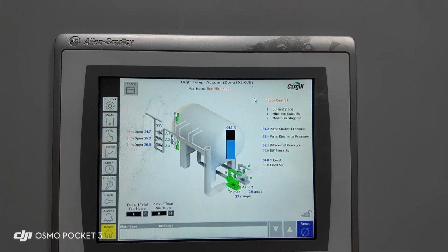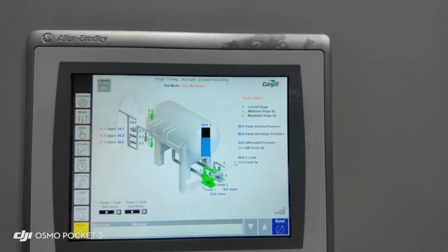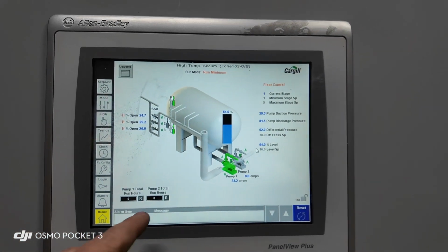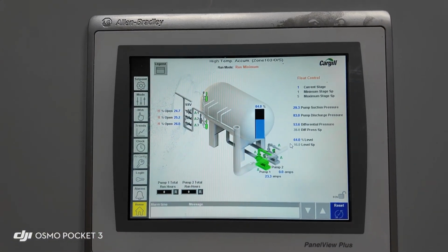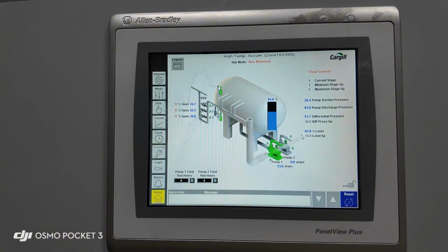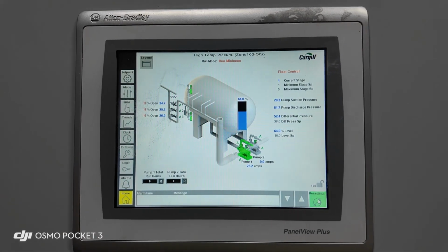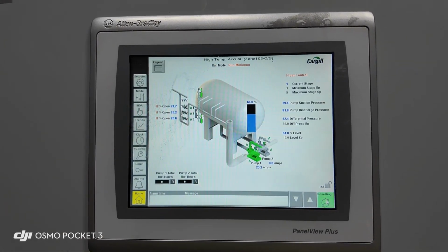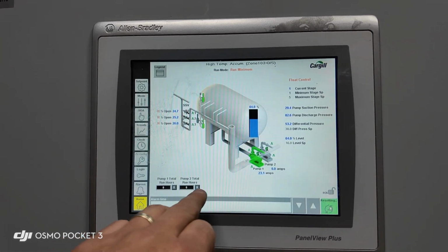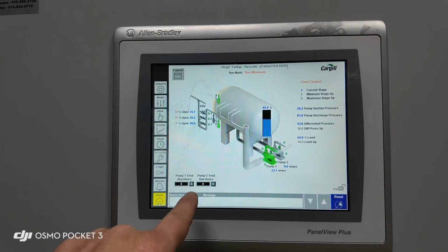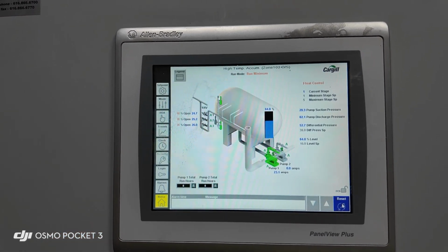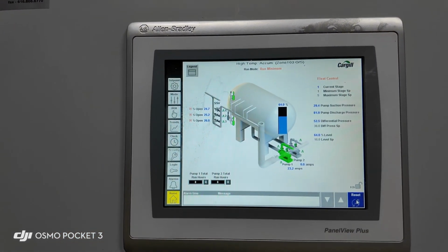Also, the vessel level is displayed graphically as well as digitally. We have the reset. This is an alarm banner on the bottom. If there were any active alarms on here, they would be displaying here. We could reset them right from here by simply pushing the reset button. These will totalize the run hours for the pumps, and the slide buttons on the side, if logged in at a high enough level, will let you reset them.